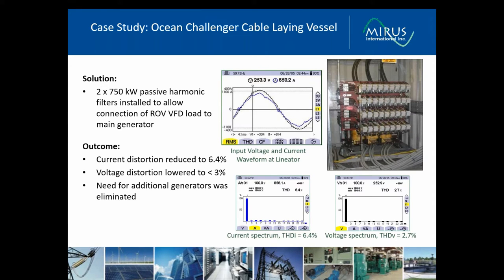After confirming the recommended solution through computer simulation, series connected filters were installed to supply the ROV VFD load. Current voltage distortion was reduced to well below the mandatory limit, even when supplied from the main generator. The customer was able to remove the additional generators, freeing up deck space, improving the equipment lifespan and saving energy. So with the filters installed, current distortion was reduced to 6.4, just a little over 6%, and running off the main generator, voltage distortion was reduced to less than 3%, well within the requirements of DNV.